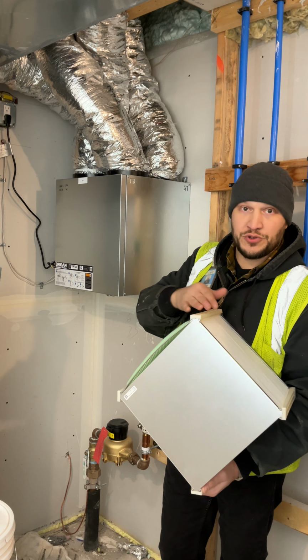Regardless of what your ventilation strategy is, it's important to confirm that you are meeting the desired airflow for your system. So here we have an ERV. In your area, you might have supply only or exhaust only system, but we are confirming across the core that we are getting a certain pressure, and then we're using the manual to confirm that that pressure is the flow we are looking for.